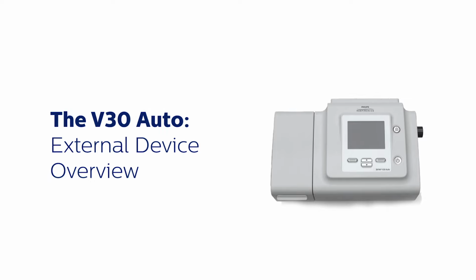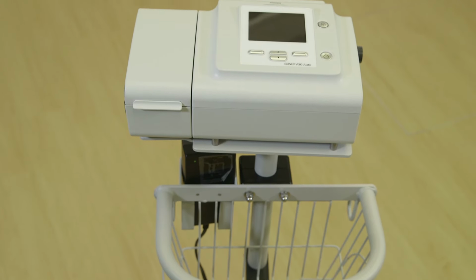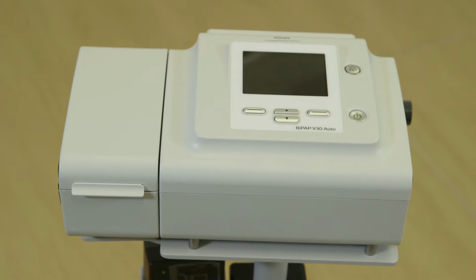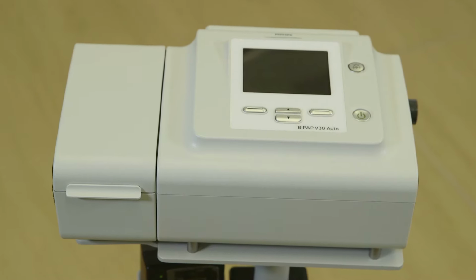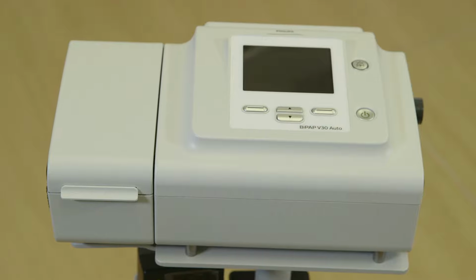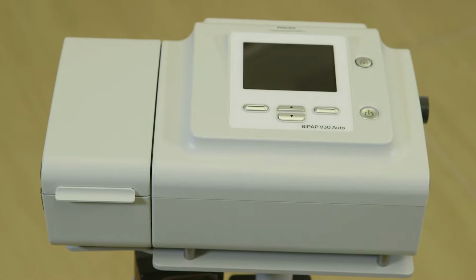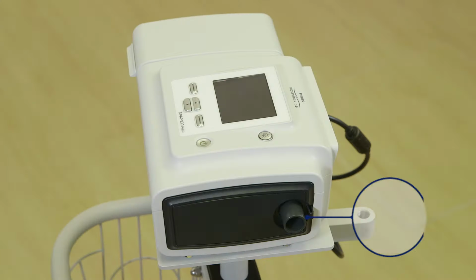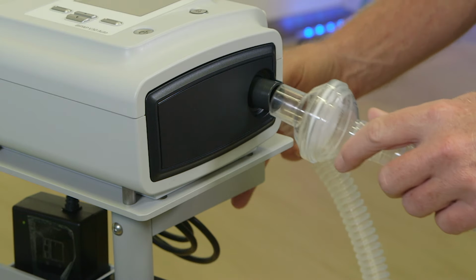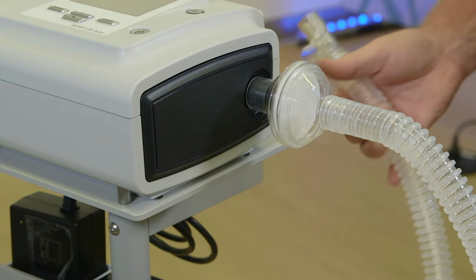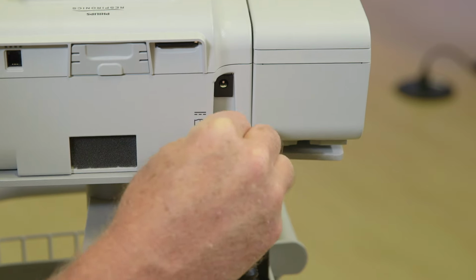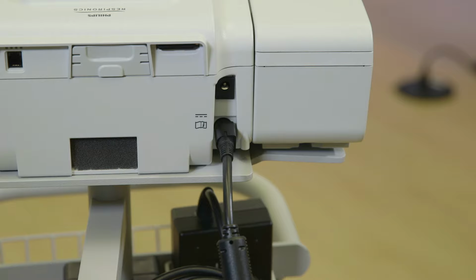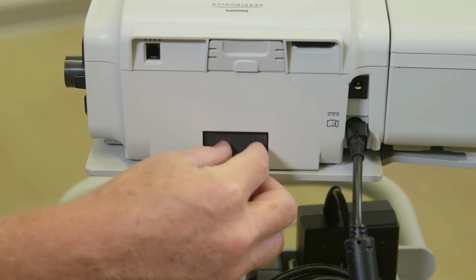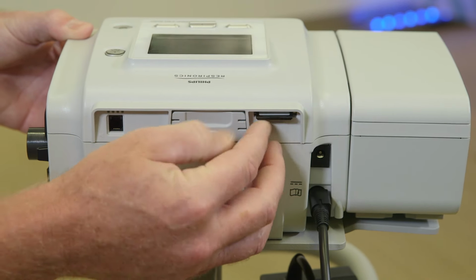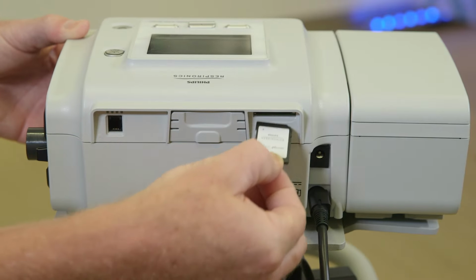Before we go deeper into setup and operation, let's take a quick tour around the exterior of the device. Beginning with the top of the device, let's first look at the screen. The graphic user interface is familiar, simple, and intuitive. The connection to your single limb circuit is to the right of the device. Install a bacteria filter here to filter air to and from the device. On the back, you will find the power cord connection, the device inlet filters, nurse call connection, and the SD card for data management and collection.